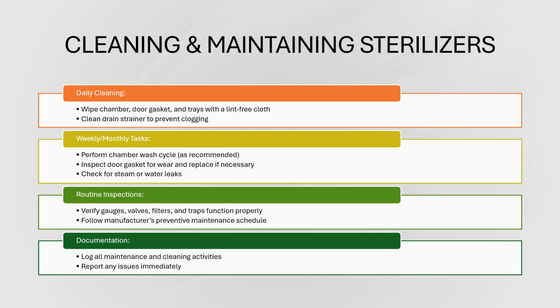So daily tasks include wiping down the door gasket. I talked about the door gasket a few slides beforehand. It's usually on the door itself or it's on the chamber. It's usually gray or black. You just wipe it down. Make sure there's no tears or rips in it as well, because then air will leak out of it. It's a quick fix. Call maintenance, have them bring down another gasket, install it, and you're on your way. Nothing too drastic about that.